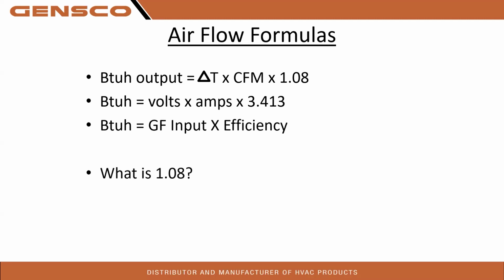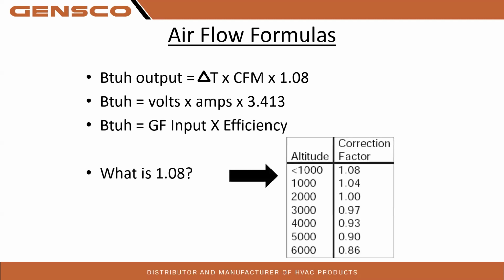So what is your 1.08? There's my altitude factor. So 1.08 up to 1,000 feet, 1,000 to 2,000 would be your 1.04. I've never been in Western Washington. I had never really had to deal with the altitude correction factor, but now taking calls in Montana and Colorado and parts of Idaho, you may need to correct your altitude factor. It goes for gas valve derating also.